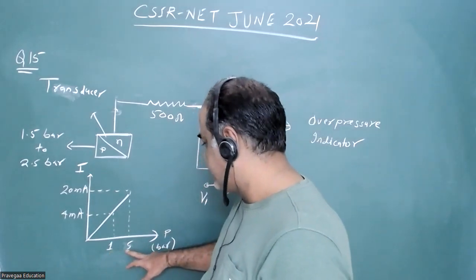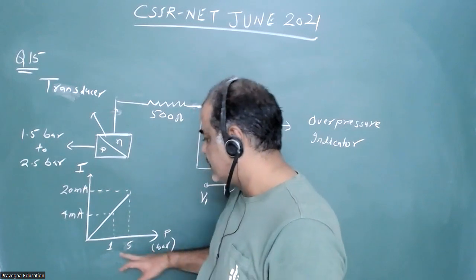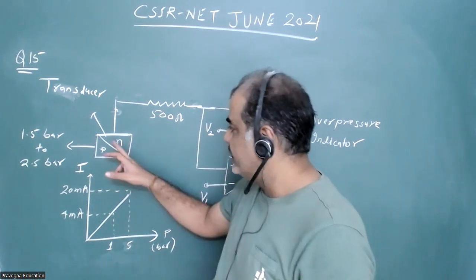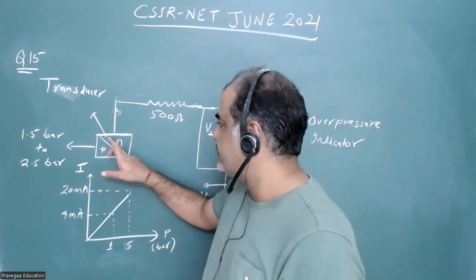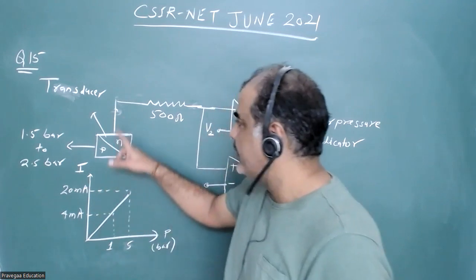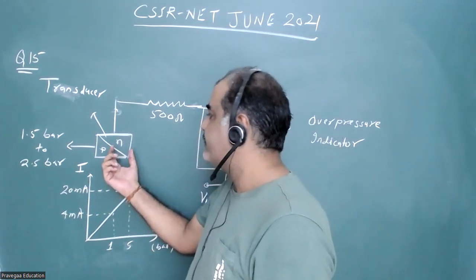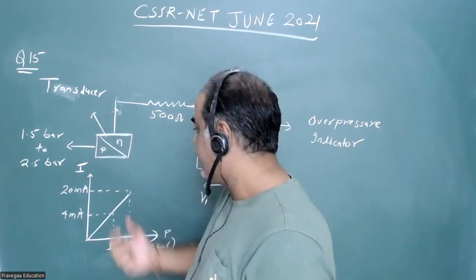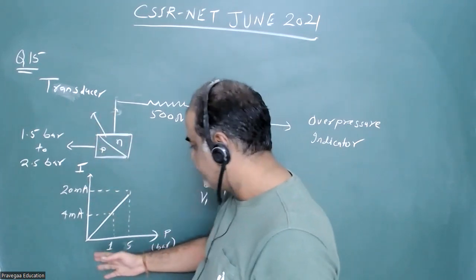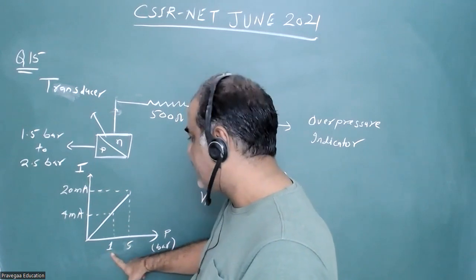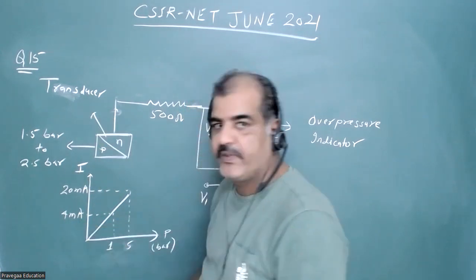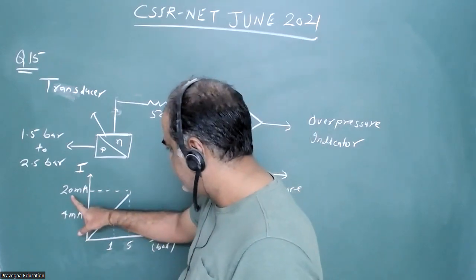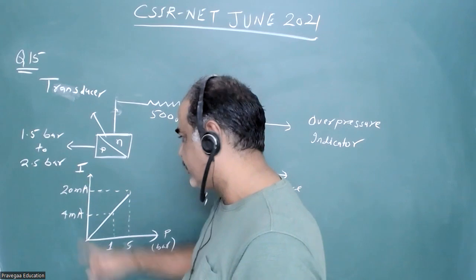It is also given that for a 1 to 5 bar range, the output of this transducer — a device which converts pressure signals into electric signals — gives us a current. When the pressure is 1 bar, the output of this transducer is 4 milliampere, and when the pressure is 5 bar, the output is 20 milliampere.